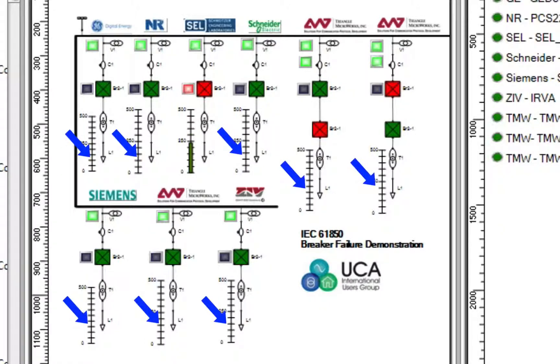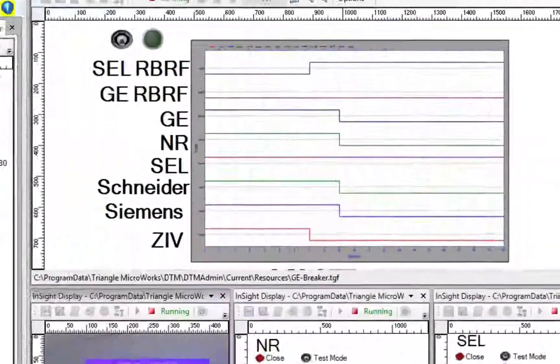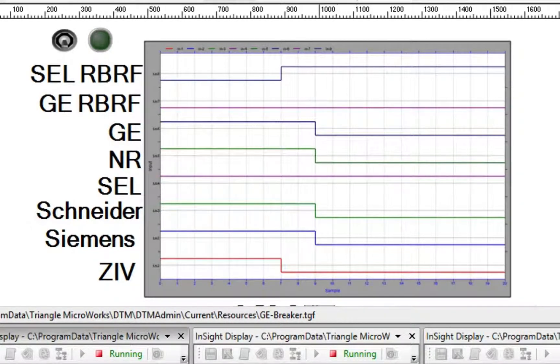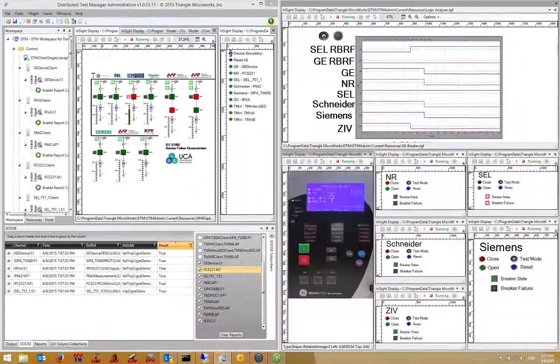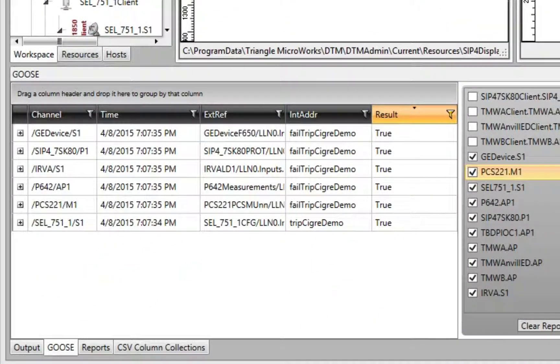Notice the current is now shown as zero for each open breaker. The logic analyzer shows the state changes. If we look at the logic analyzer, we can see that each of the simulated breakers has changed state. This is useful for seeing the relative timing of signals in the simulation. Looking at the Goose report log in DTM, we can see that each of the simulated breakers received the RBRF Goose message from the simulated Schweitzer device.